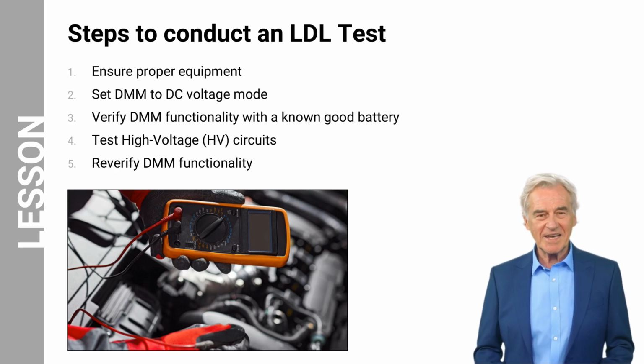Here is an overview of the guidelines of the LDL, steps to help prevent electrical hazards and ensure a safe working environment. Step 1. Ensure the use of proper safety and tool equipment. Step 2. Set the DMM to the DC voltage mode. Step 3. Verify the functionality of the DMM with a known good battery. Step 4. Test the HV circuits. Step 5. Re-verify the functionality of the DMM. We will now look at these steps in detail.